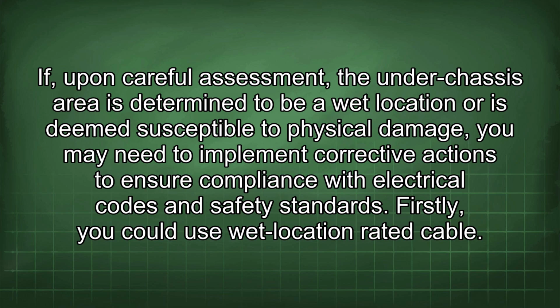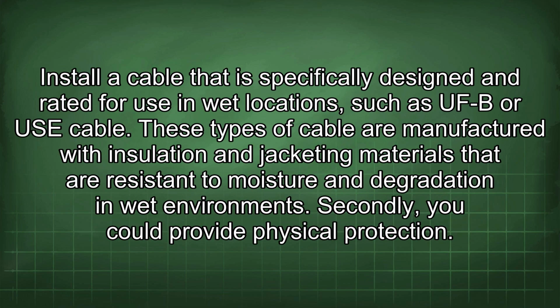If, upon careful assessment, the under-chassis area is determined to be a wet location or is deemed susceptible to physical damage, you may need to implement corrective actions to ensure compliance with electrical codes and safety standards. Firstly, you could use wet location rated cable. Install a cable that is specifically designed and rated for use in wet locations, such as UF-B or USE cable. These types of cable are manufactured with insulation and jacketing materials that are resistant to moisture and degradation in wet environments. Secondly, you could provide physical protection.